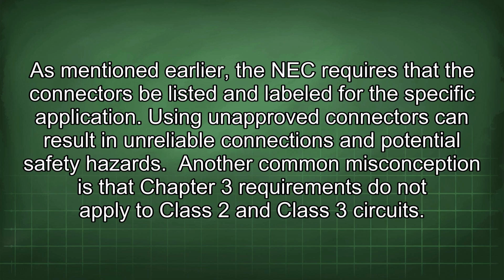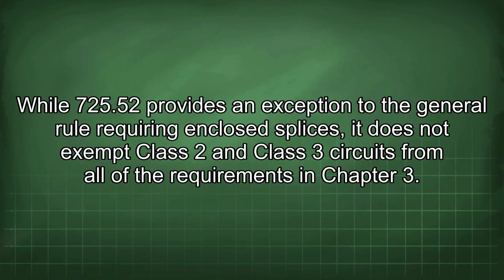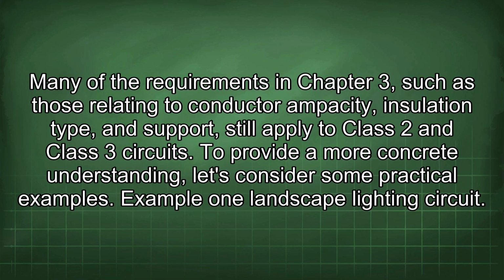Another common misconception is that Chapter 3 requirements do not apply to Class 2 and Class 3 circuits. While 725.52 provides an exception to the general rule requiring enclosed splices, it does not exempt Class 2 and Class 3 circuits from all of the requirements in Chapter 3. Many of the requirements in Chapter 3, such as those relating to conductor ampacity, insulation type, and support, still apply to Class 2 and Class 3 circuits.